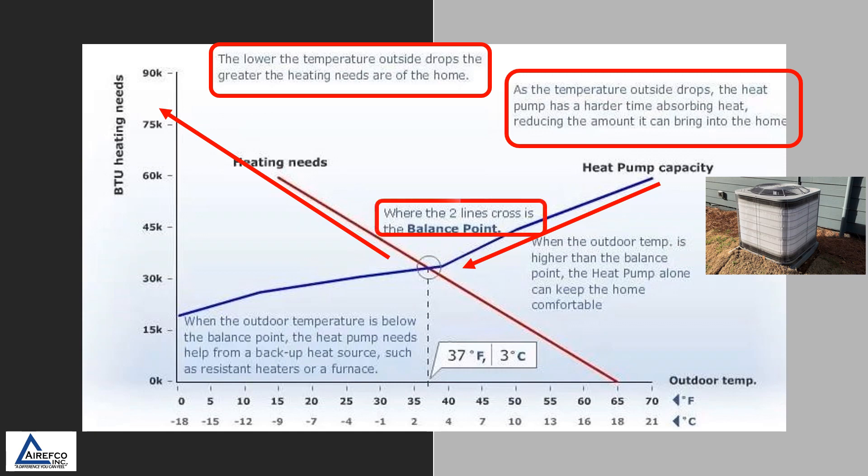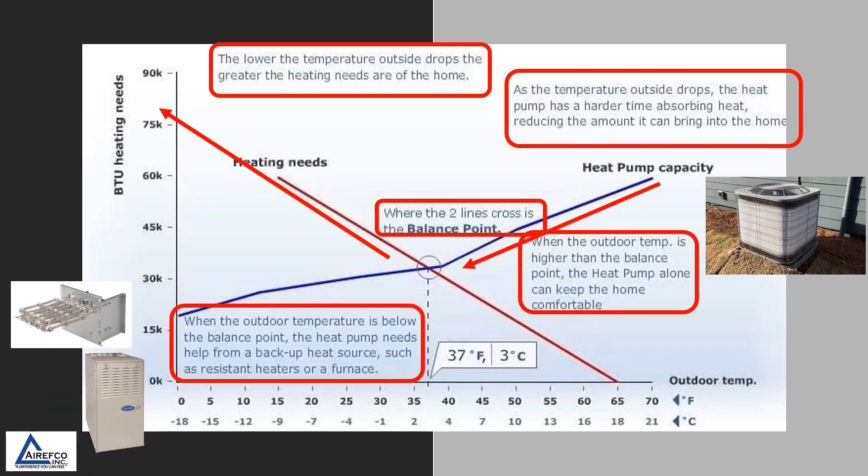Where the two lines cross is the thermal balance point. When the outdoor temperature is higher than the balance point, the heat pump alone can keep the home comfortable. When the outdoor temperature is below the balance point, the heat pump needs help from backup heat sources such as resistant heaters or a furnace.